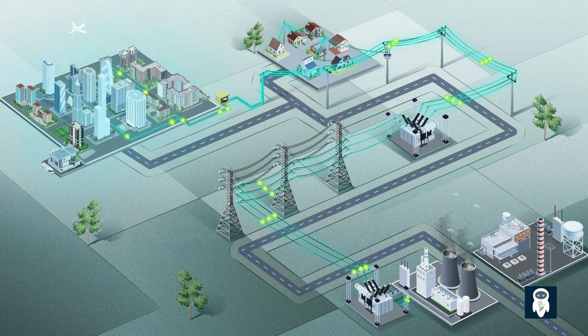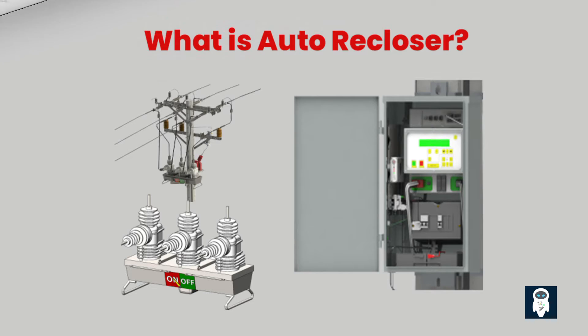An automatic recloser is a device used to automatically restore power to a distribution line after a temporary outage. It is designed to automatically detect faults and interrupt the flow of power. Once the fault is cleared, the recloser automatically turns back on and restores power. If the fault still exists, the auto recloser is locked out to protect the system.